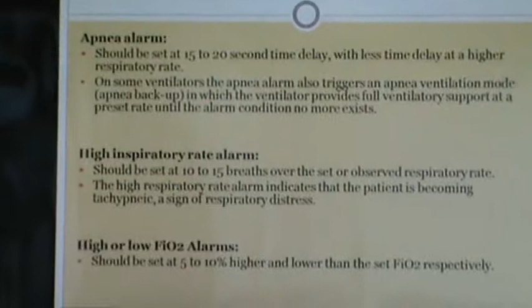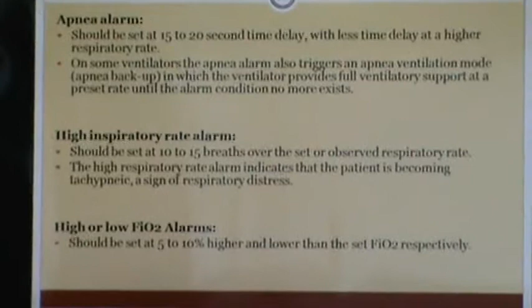High inspiratory rate alarm. This is generally set 10 to 15 breaths over the observed respiratory rate. A high respiratory rate indicates either the patient is becoming tachypneic or is a sign of distress, and if there is water settling in the circuit, that will cause false triggering, and you will get the high rate alarm.